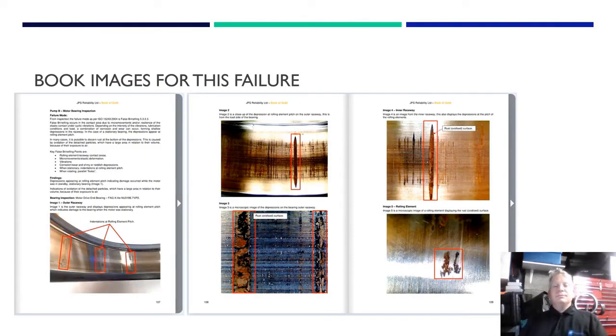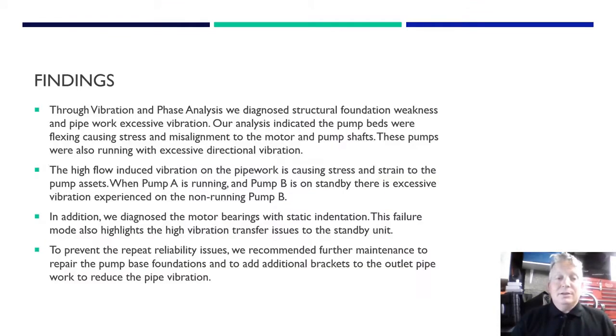That's the physical bearing inspection done. We'll jump back into the presentation and go over the conclusions of why and what we found. Vibration analysis and phase measurement - on this motor you can put two transducers and do cross-channel phase. If you put a transducer on the motor and one on the bed frame and watch the phase change, it means the structure is pulling apart. So you can map out the movement to determine what the pump and base is doing. We could then say the root cause of your motor bearing failure, your pipe cracking, and your flanges going is because the base is too weak.